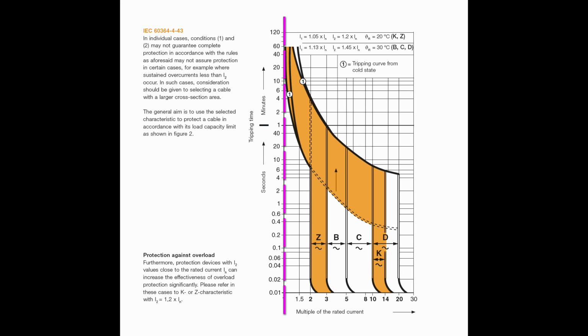Now on the left of the graph there, you can see the actual time in seconds or minutes right at the top there. And that's actually how long it would take to trip for any particular current. So you can see that the first part of the graph, starting by about 0.02 seconds and going upwards, is virtually sort of vertical. So essentially in those cases it's going to trip nearly instantaneously, sort of 0.02 seconds or whatever. And of course that's the whole intent of these devices, that once you get to the specific current you've got, then it will actually trip.